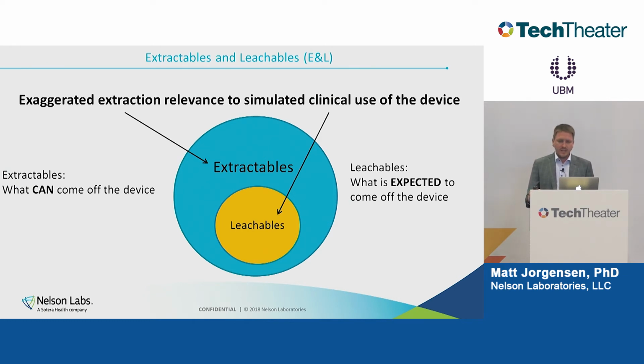Just to be clear, because I'm going to spend a couple of slides talking about chemistry testing, I'm going to use the words extractables and leachables. Extractables are chemicals or compounds that can leave the device when exaggerated and aggressive conditions are used. Leachables, on the other hand, are what can leave the device and contact the body under simulated or clinical use conditions. Ideally, if the experiment is set up well, everything that's an extractable would also be a leachable, but depending on the device, they might not overlap perfectly.